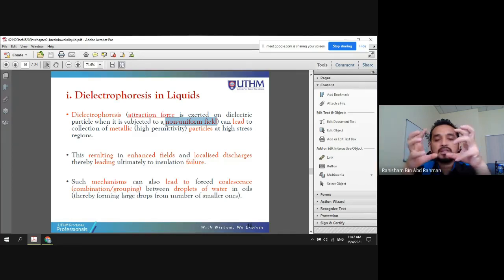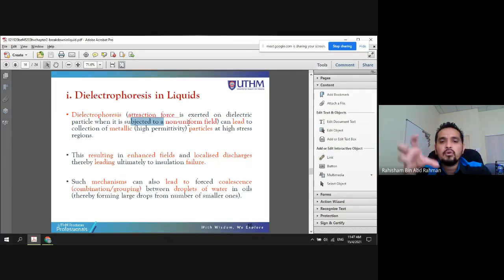It could happen due to the formation of ionization within the material, or due to the movement of oil carrying metallic particles, among many other causes. This non-uniform electric field will trigger what we call an attraction force. Once dielectrophoresis happens, this attraction will pull and attract more and more metallic particles within the liquid, and they will deposit on a certain base, which will trigger discharge activity within the liquid dielectric.